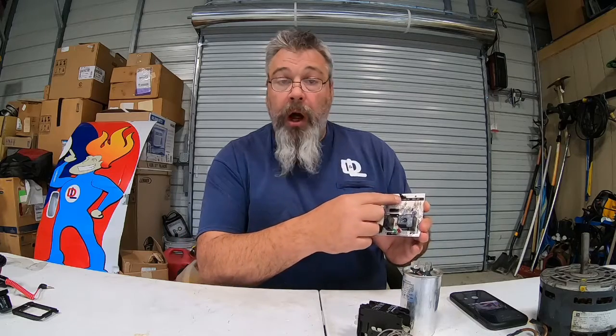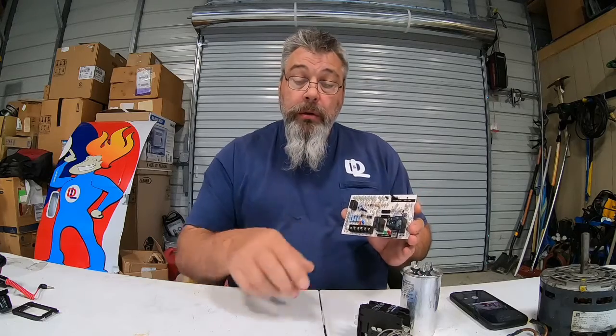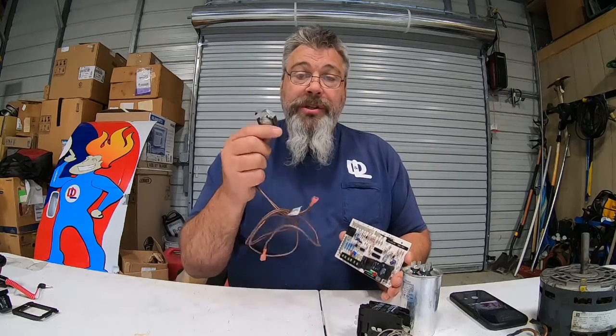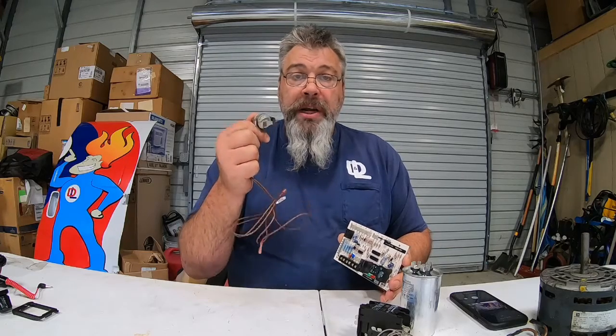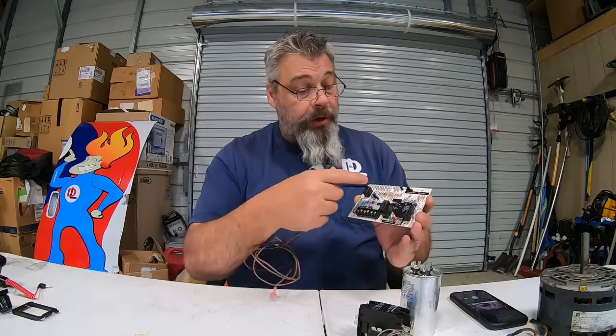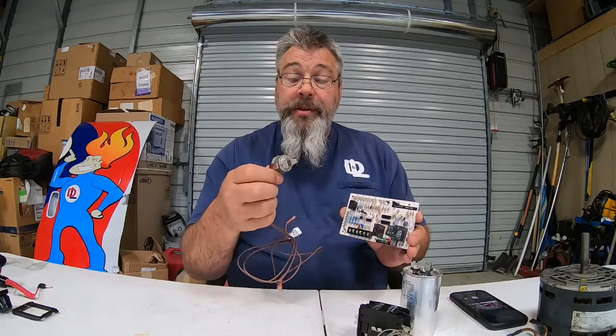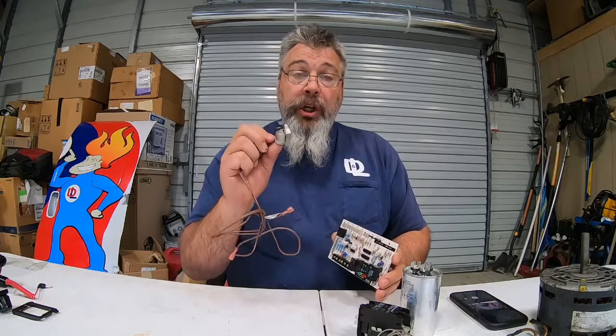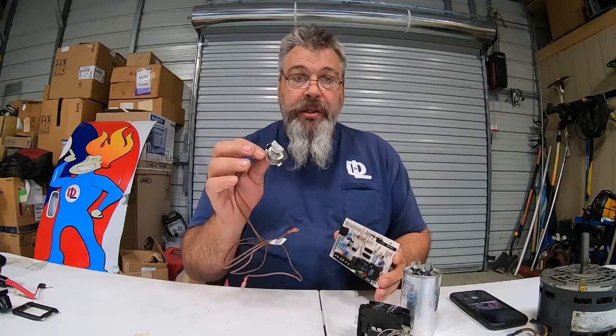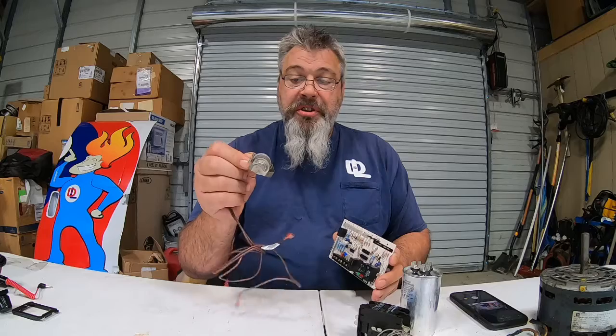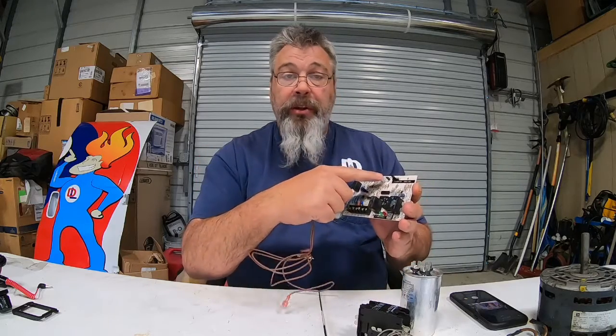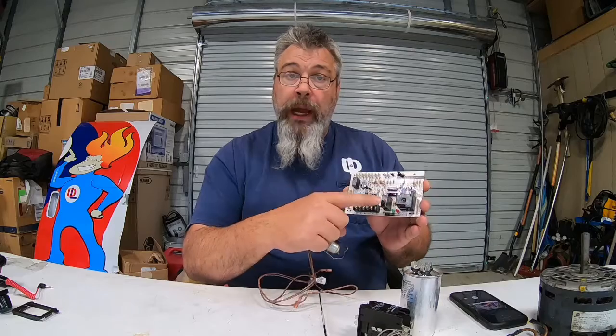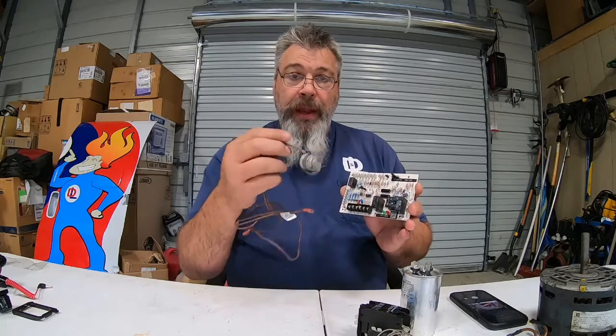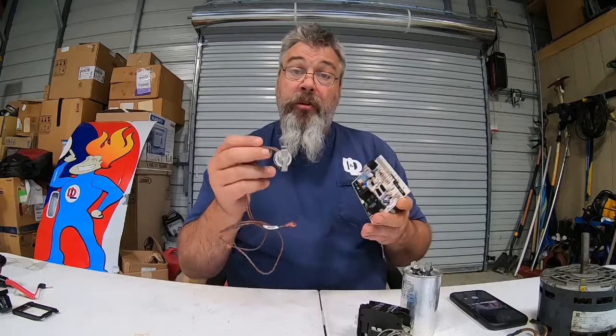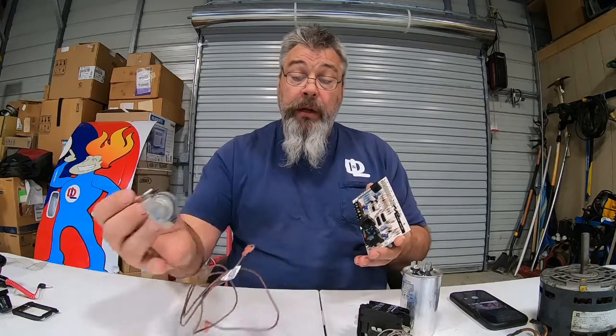This board has a timer on it that goes from 30, 60, or 90. And temperature. We have what we call a defrost sensor on the line of the condensing coil. This defrost sensor plugs right into the board under DFT. What that does is it takes the line temperature and converts it to ohms of resistance. Once that ohms of resistance is met, it is sent through these wires into this board, sent to a relay, and that relay energizes.